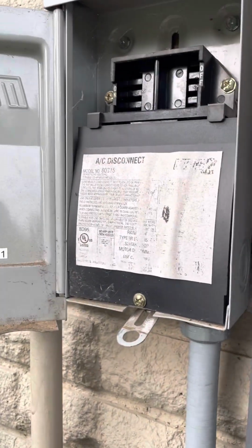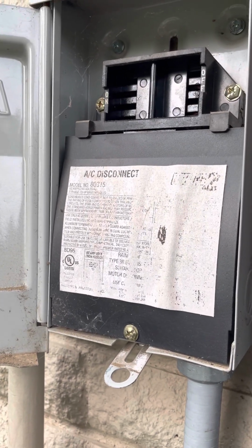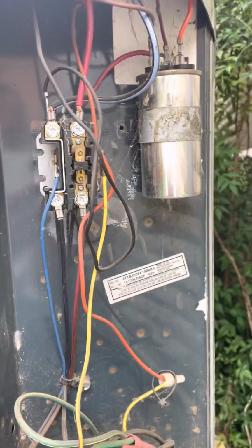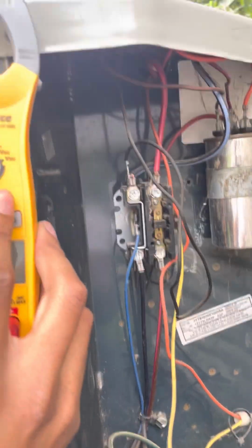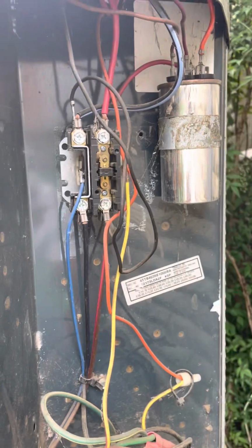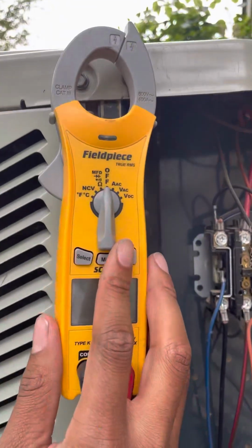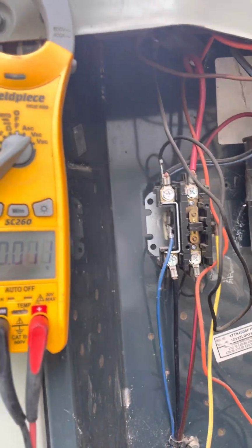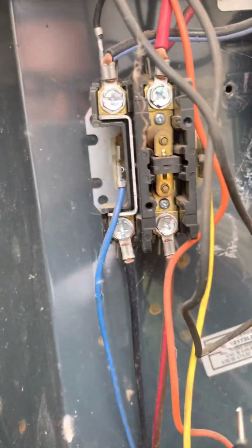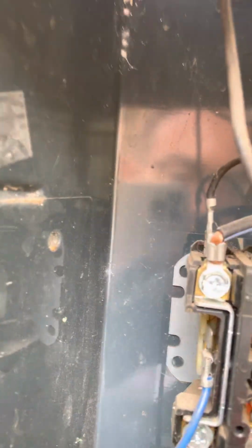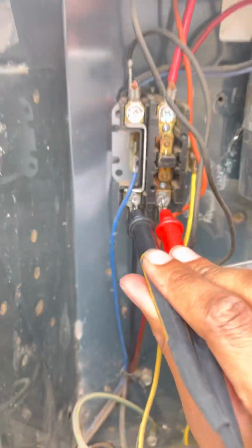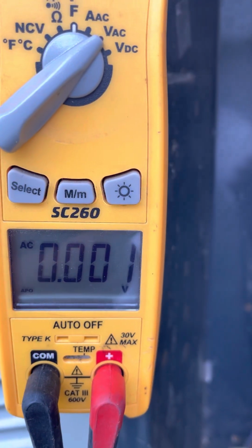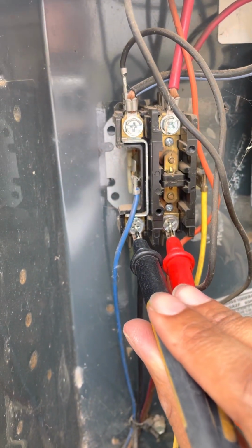So we have the power disconnected. There's the disconnect, and then we see we have it disconnected. So we should have no incoming power or high voltage. But it's always important to check and confirm, because sometimes disconnects fail. So let's take our meter here. We're going to set it to volts AC, and check to see if we have any high voltage. It should be around 240 volts, but as you can see, we have 0 volts. So that disconnect is working properly.